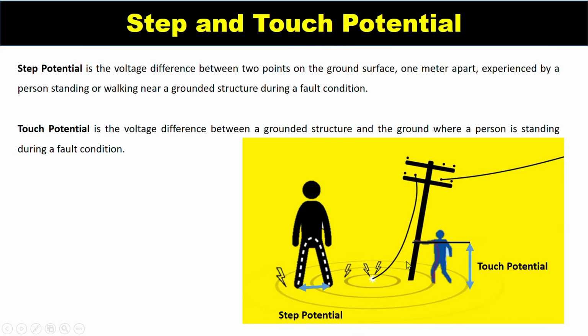When a fault occurs, it creates voltage rings in the ground. Each ring has a different voltage. When a person is standing on the ground, one foot is on one ring and the other foot is on another ring. There exists a potential difference, and this potential difference is called the step potential. And when a person touches the grounded structure, the voltage between the feet and the hand is called the touch potential, because the person is touching the grounded structure.